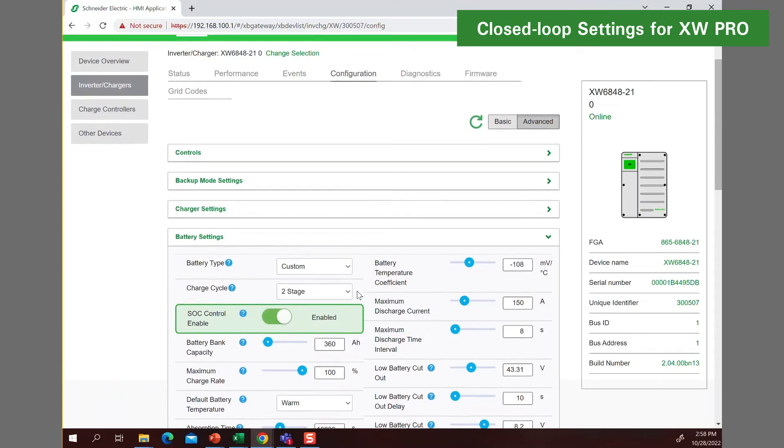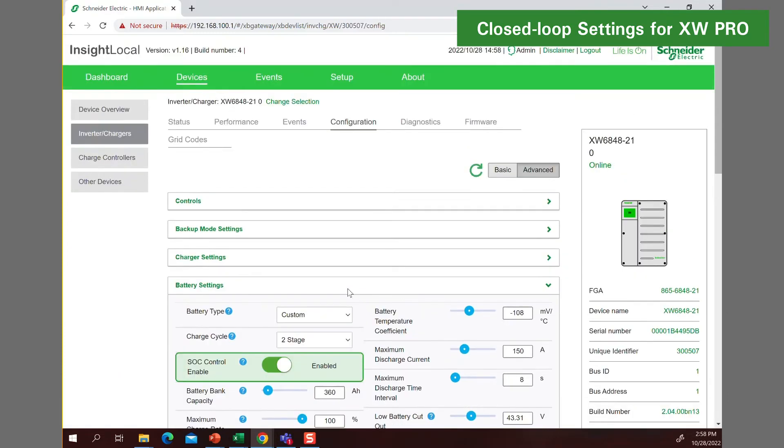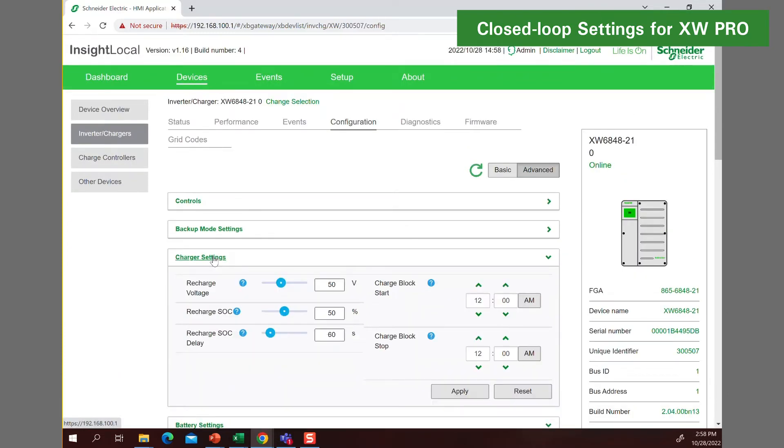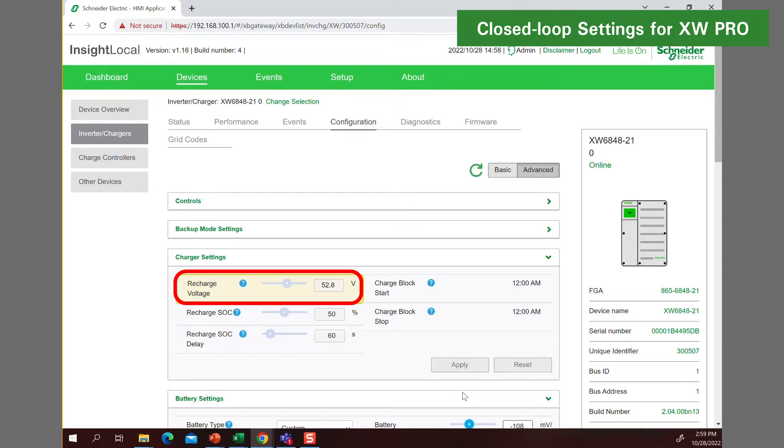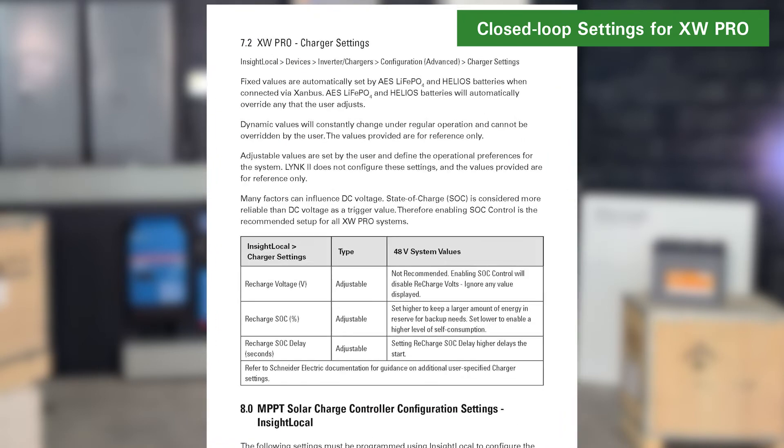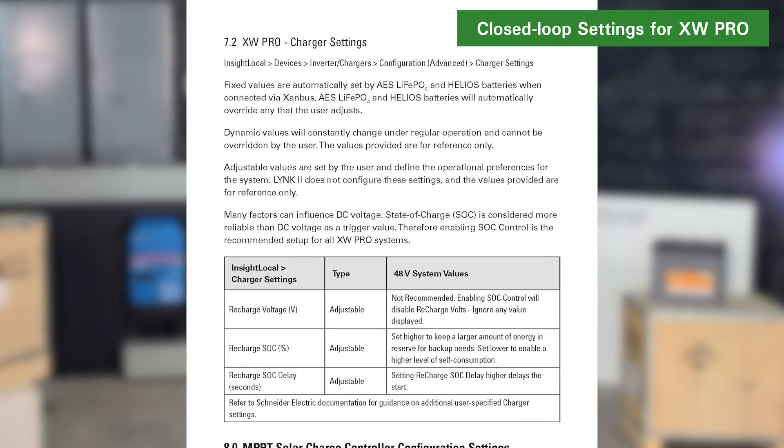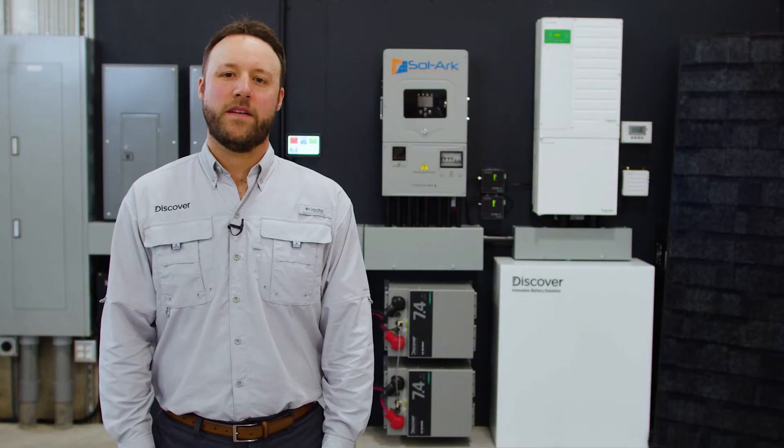The next step involves programming the charger settings. Setting recharge SoC to a higher percentage keeps a significant amount of energy in reserve for backup needs. Setting it lower enables a higher level of self-consumption. Section 7.2 of the LYNK II XW Pro User Manual reviews all the charger settings.